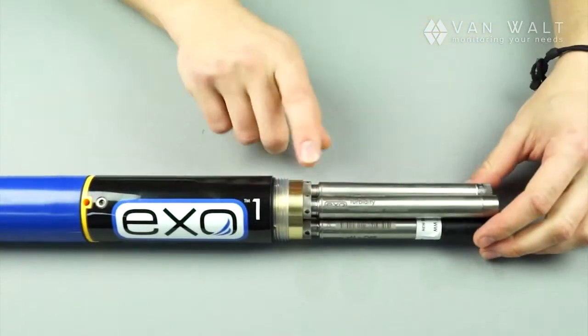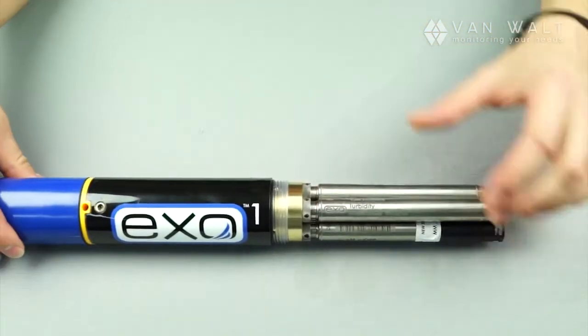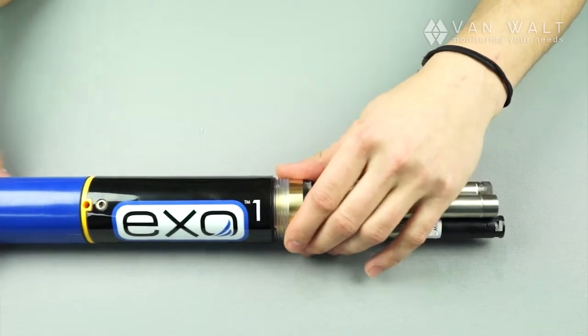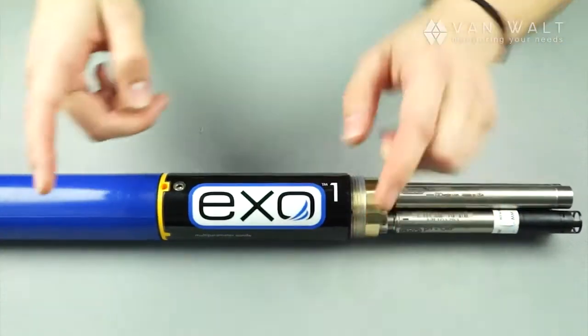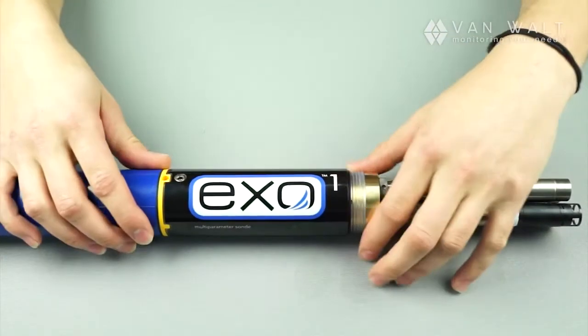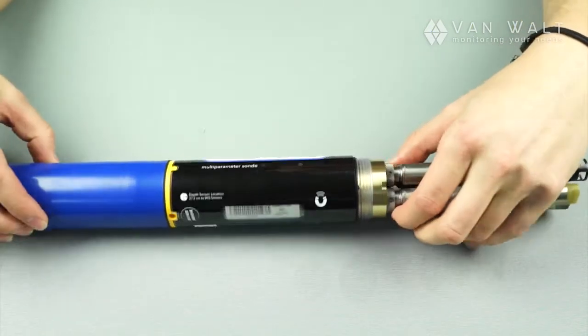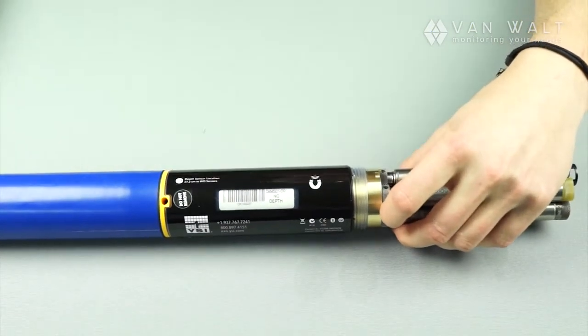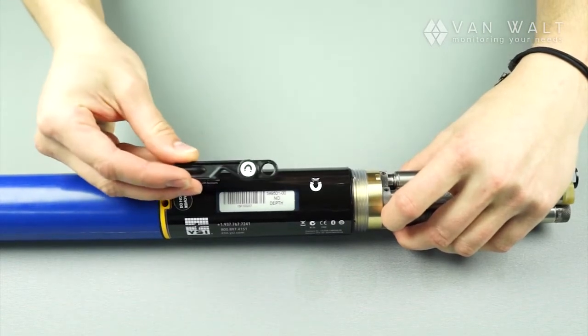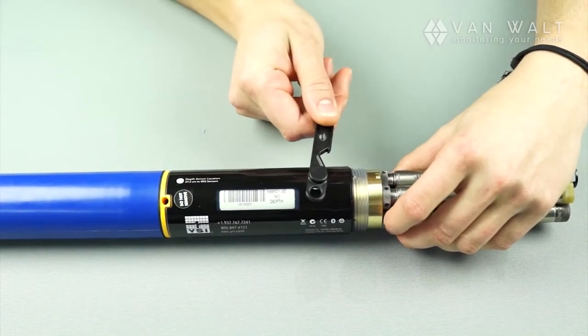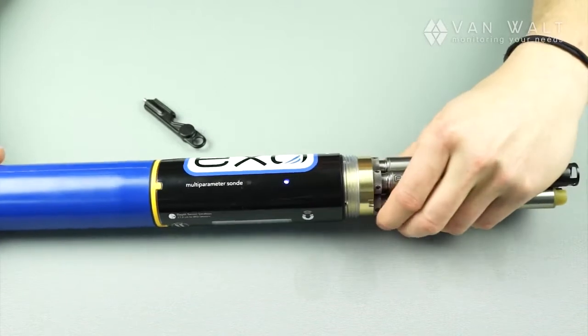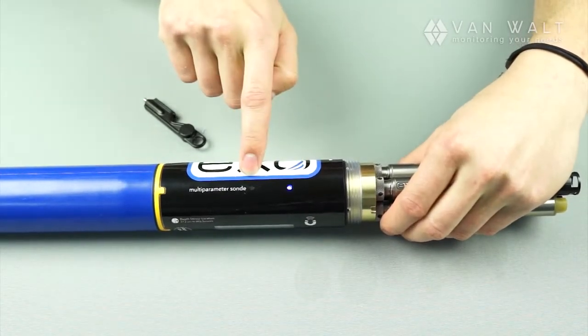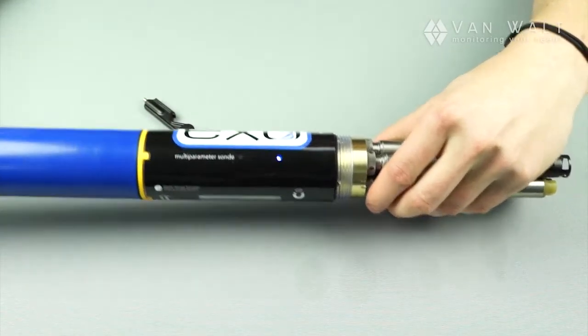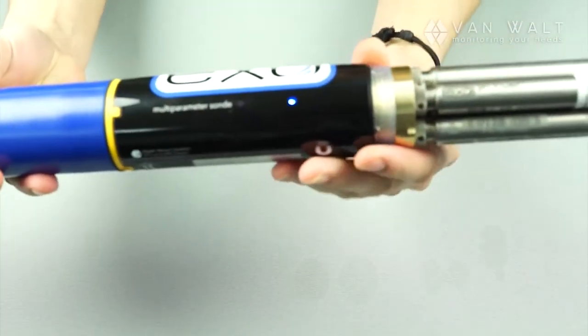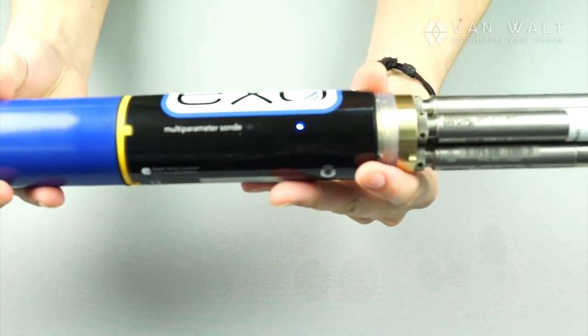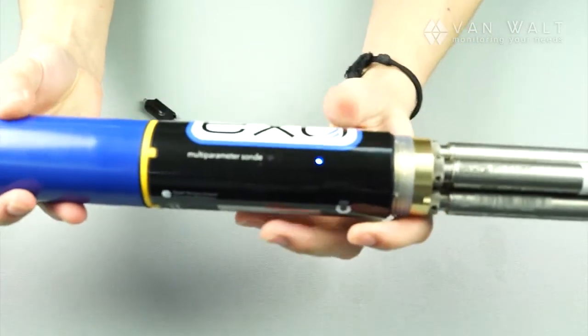So if we move along from our probe end, obviously this is the titanium bulkhead. Next we get to the main body of the unit where the logging is done. The only controls that we need on this unit are this little magnet here and the magnet that's on the key we looked at earlier. By touching the 2, we get a LED here that tells us it's on and the unit is logging. All of our pre-programming for that has been done with the KOR software on the PC.